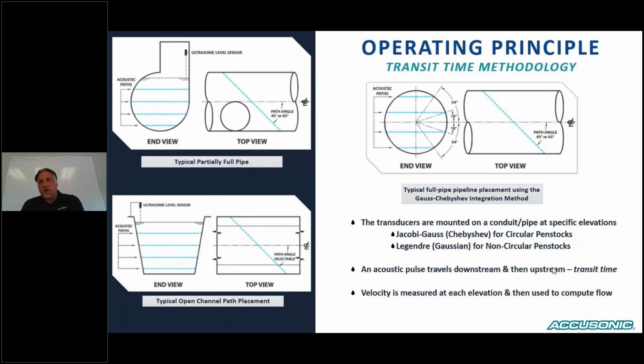Switching gears and going into the operating principle, this is transit time ultrasonic flow measurement. So the methodology here is, again, transit time. In the hydroelectric industry, we're typically dealing with full pipes. So we have 2 main integration techniques that we use for full pipe applications, and it's what we call the Chebyshev integration. That's for all circular penstocks, and we use the Gaussian integration for anything that's non-circular, whether it's a rectangular conduit, a square conduit, horseshoe tunnel, anything full pipe.